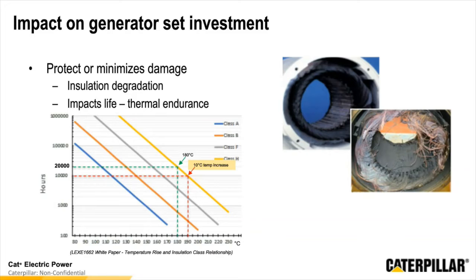That would be a typical application for a standby generator set. Now, if the generator is operating for prolonged periods of time with an overcurrent or above the typical rating, it's going to see an increase in temperature, and at 10 degrees Celsius of an increase, as we said, you're going to halve that life. So now you're getting around 10,000 hours of life instead of the 20,000 that was expected. That degradation isn't an instantaneous failure, but eventually you get to a point where you cause weaknesses within the system, and it could potentially cause a failure that could cause the entire generator to have a short and end up being a catastrophic failure. So we want to make sure that we're protecting that asset and that we're getting the most life out of the investment that we've made.